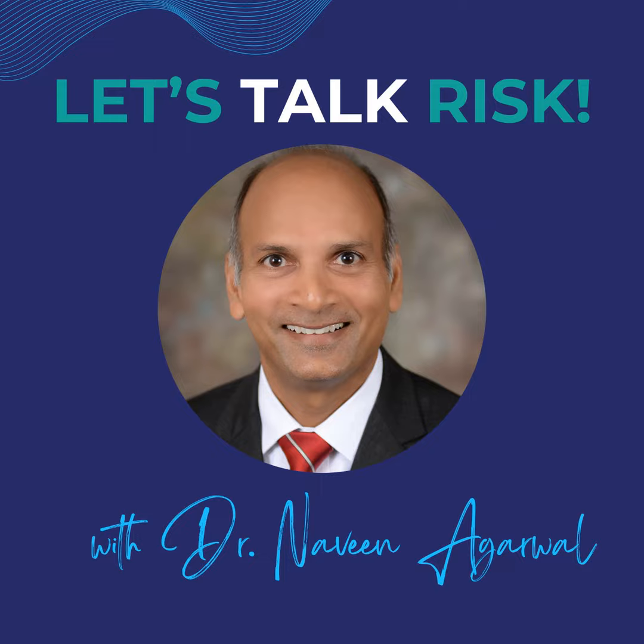how am I going to evaluate this as I design? Is that my clinical study or some other evaluation, if I understand complacency? But then if that's also a risk in post-market, that gives me a chance to think about how I want to monitor for that in post-market. Is there a way I can do that with my existing pool of customers, or is that something I need to rely on literature reviews for? So what am I looking for? Capturing that as early as you can in your risk analysis, or advocating for thinking about use-related risks for your AI devices early, is just going to give you a better chance to build that in and be able to capture those more quickly when they happen.